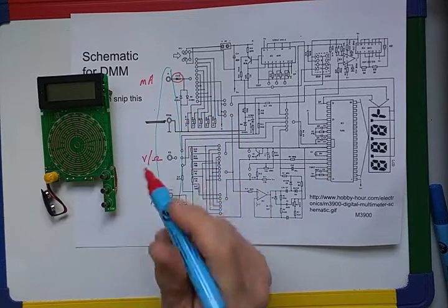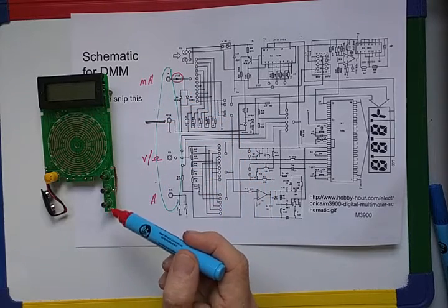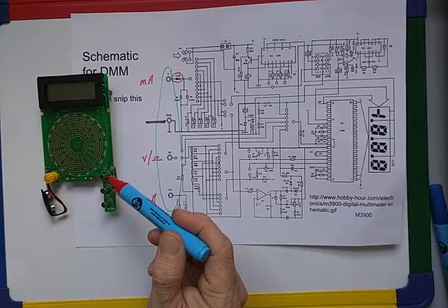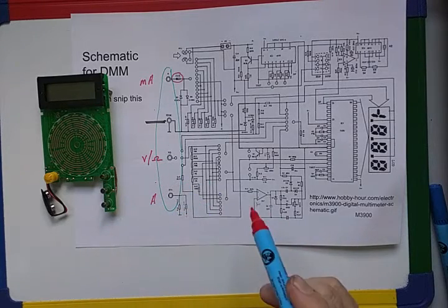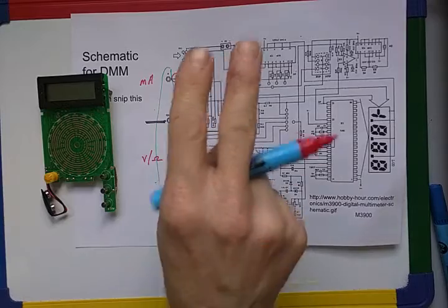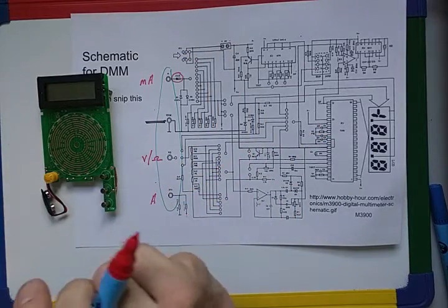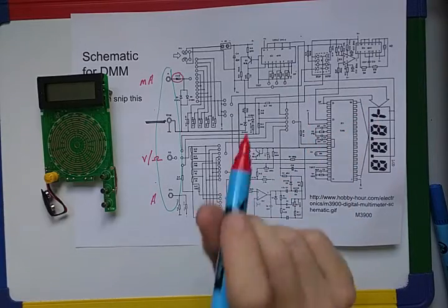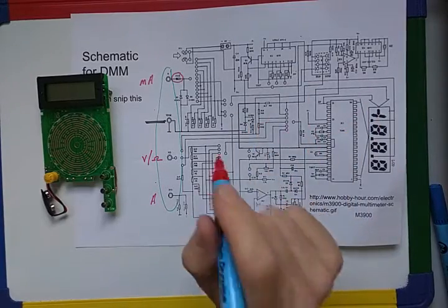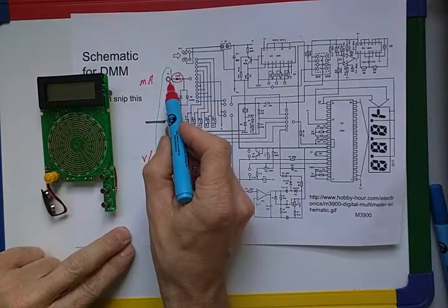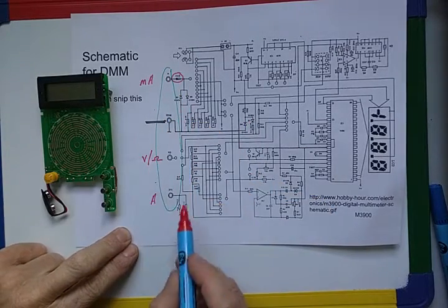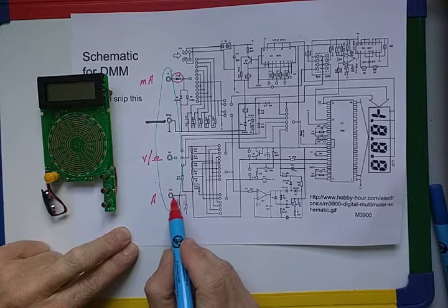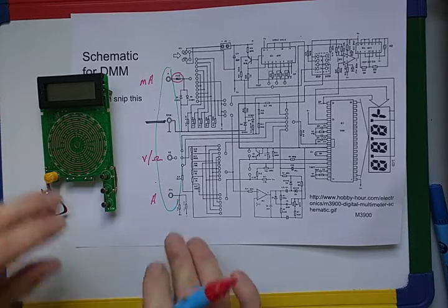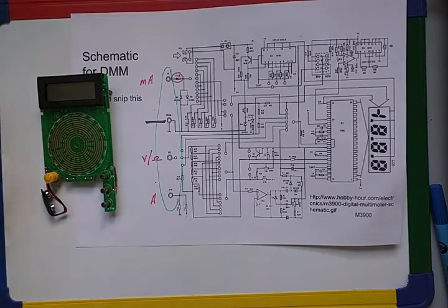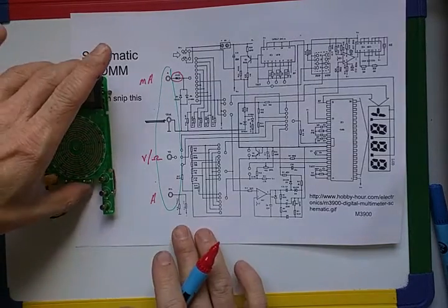The upshot of that is that if you mistakenly have your leads plugged into COM and current, as if you're going to measure a current, and you then put them in to measure a voltage, let's say on a 230 volt socket outlet, you've essentially put a short circuit across the socket outlet. So you've got to have some sort of fuse inside the meter that's going to blow there for safety. So you'll see a fuse there on the milliamp range. On this particular meter there is no fuse in the 20 amp range, which is bad. You don't want to use a meter out in industry that doesn't have fuses on both current ranges.